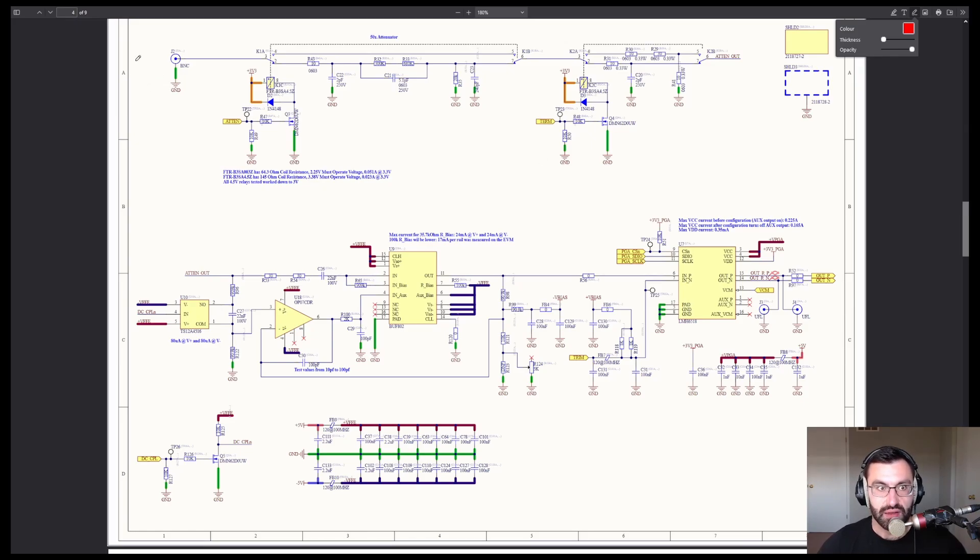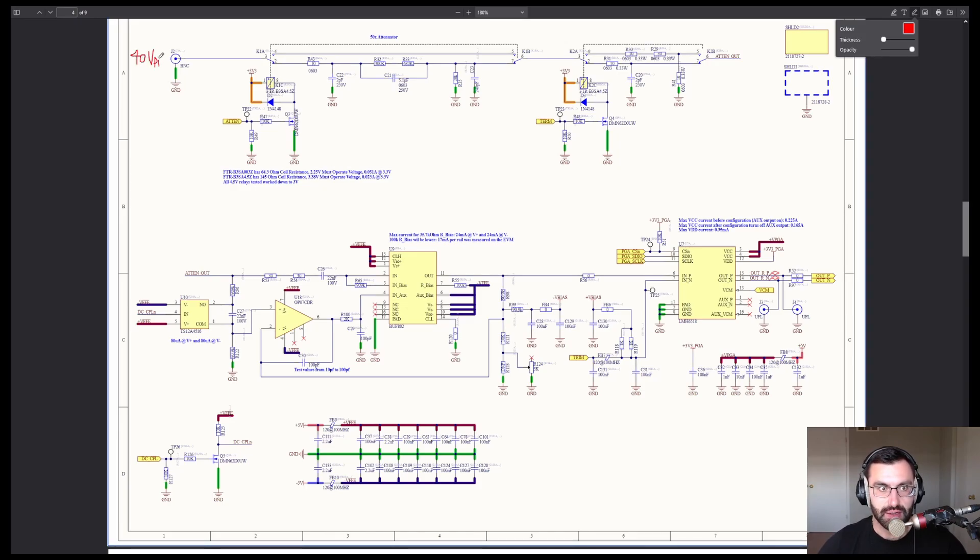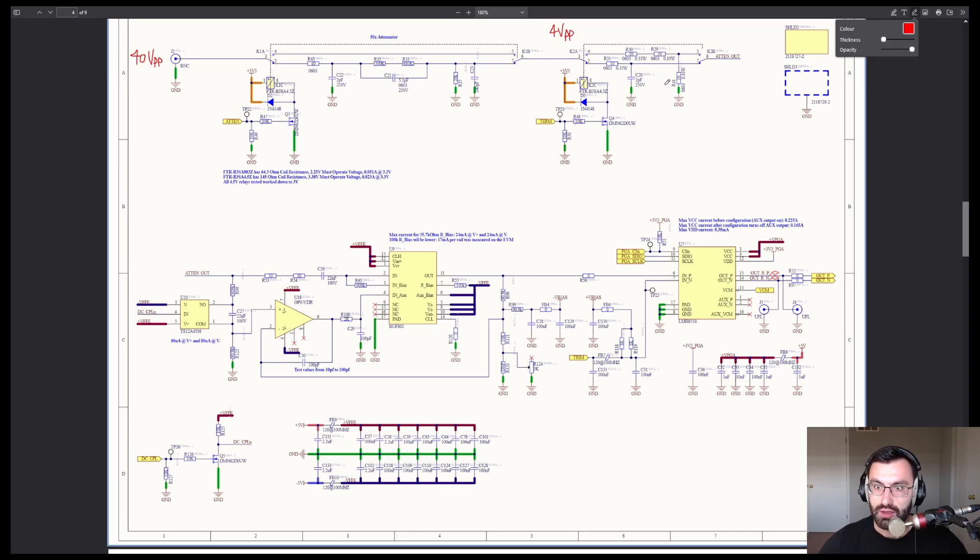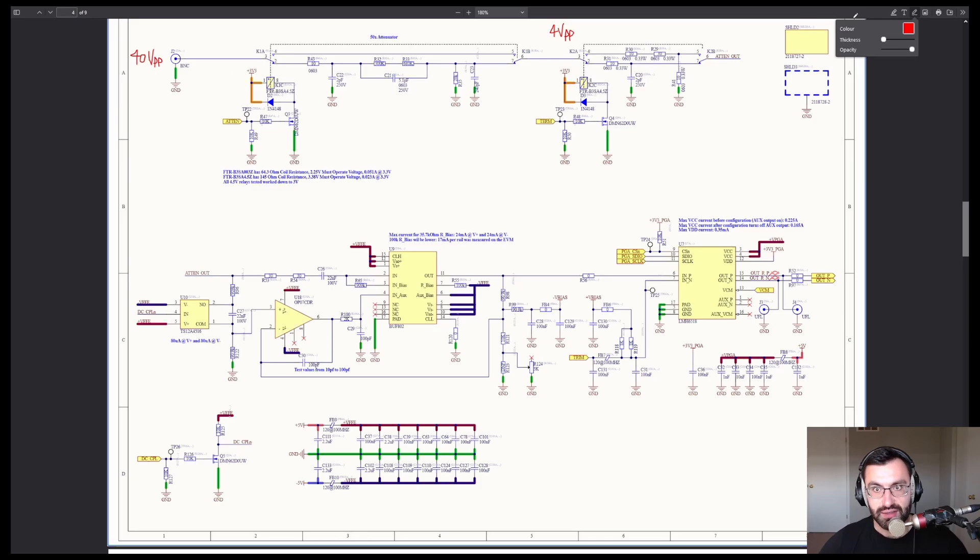As we mentioned in the last video, the maximum measurement range is 40 volts peak to peak for the 1 megaohm path, and 4 volts peak to peak for the 50 ohm path. Now the question is, how much higher than this can you go without really starting to break things?